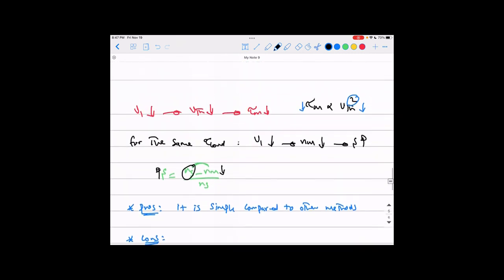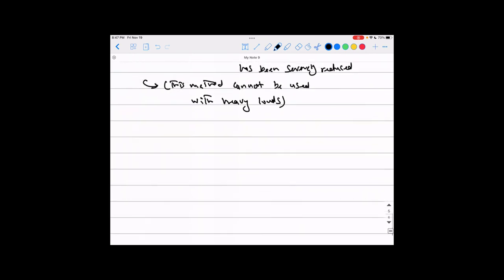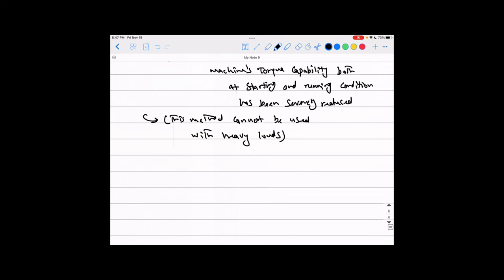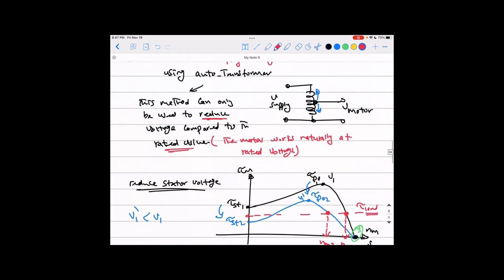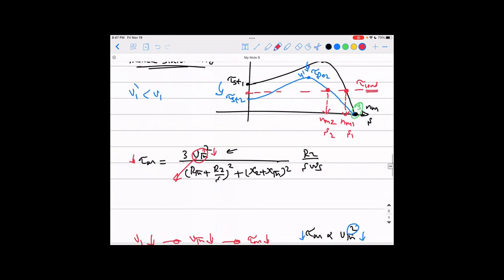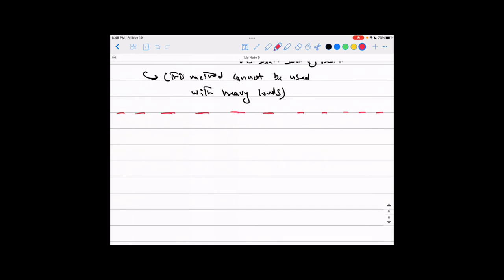With those previous two methods — adding resistance to the rotor circuit and reducing the stator voltage using an autotransformer — yes, you can reduce and control the speed. But in both cases we did not change the synchronous speed of the machine. So any reduction in speed translates into increasing the slip, which increases rotor copper losses and kills the machine's efficiency. What if we instead play with the synchronous speed of the machine?